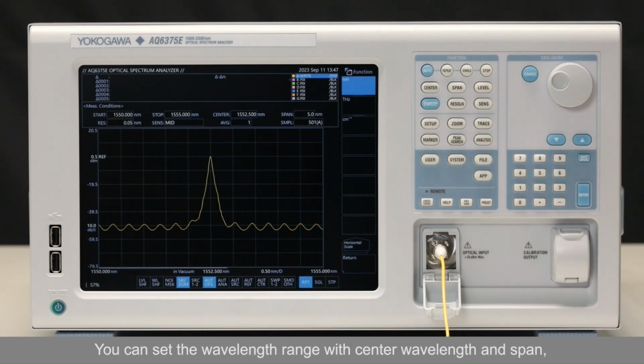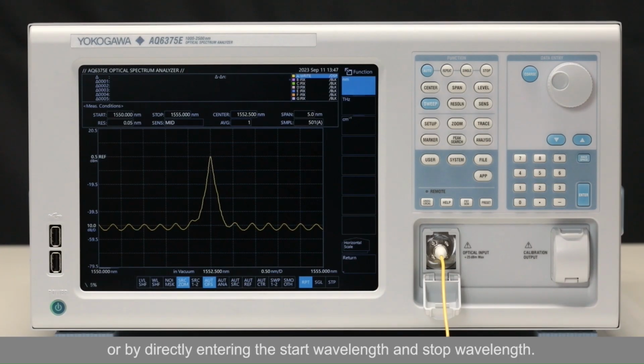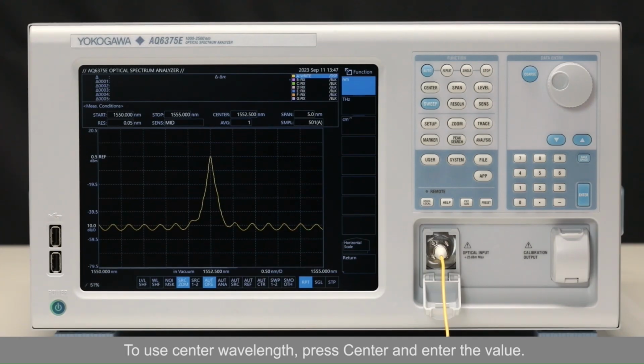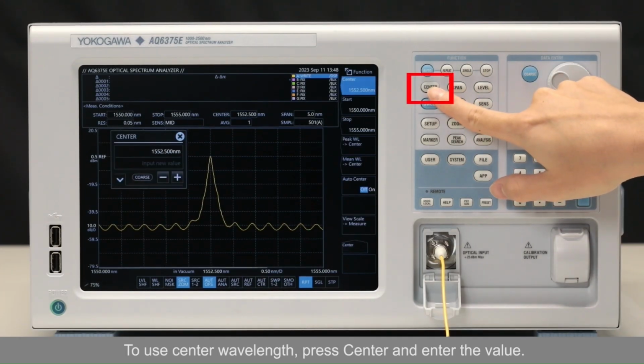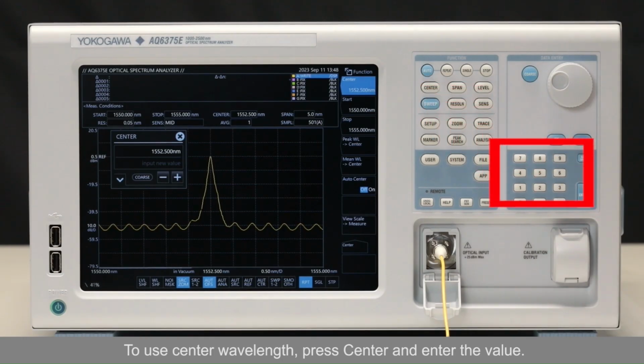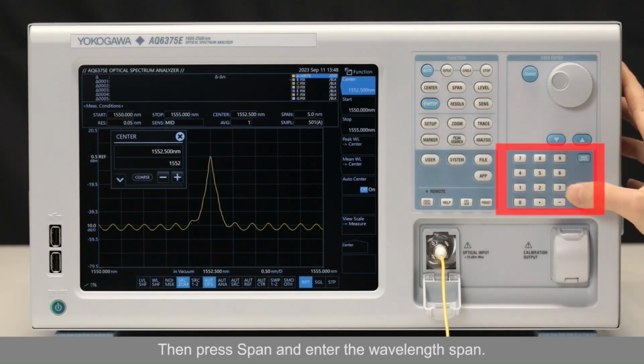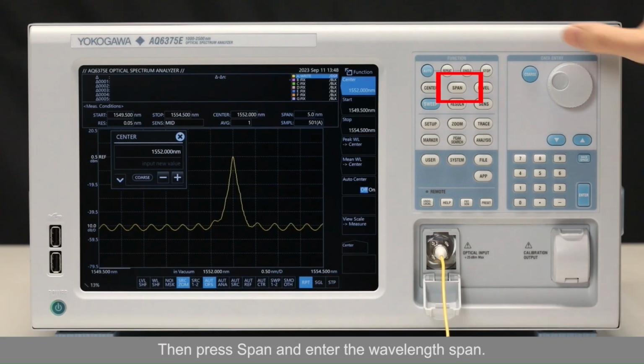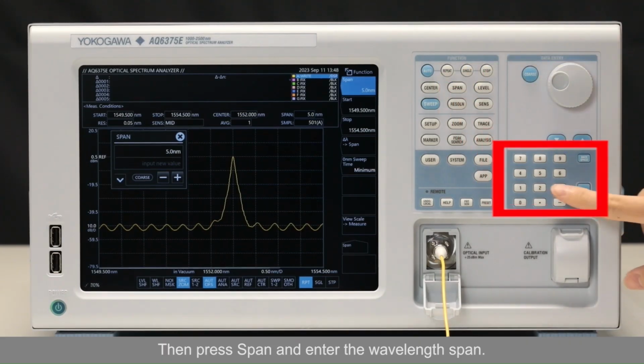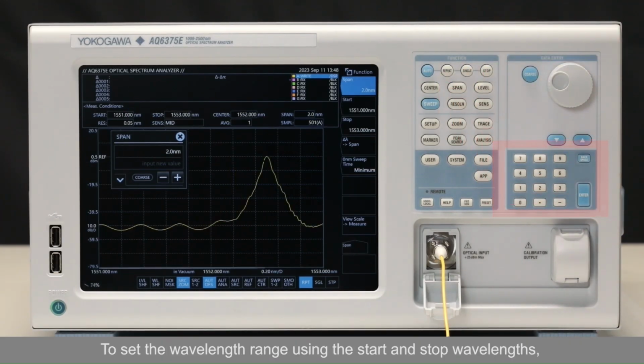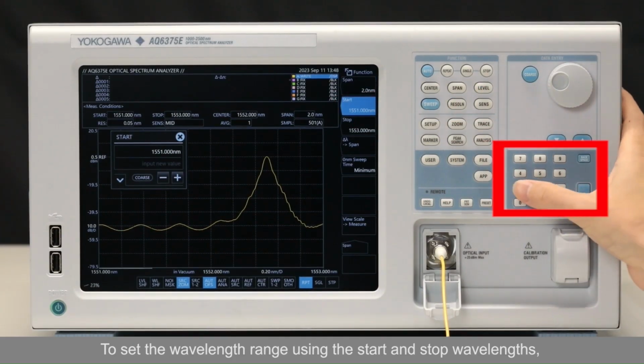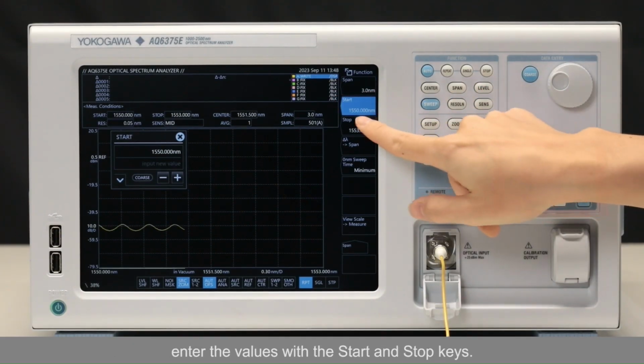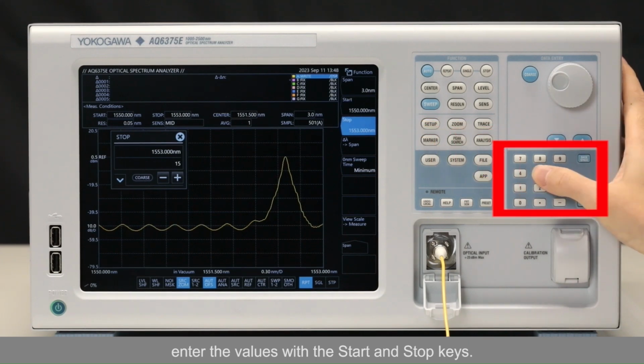You can set the wavelength range with center wavelength and span, or by directly entering the start wavelength and stop wavelength. To use center wavelength, press the center button and enter the value. Then press the span button and enter the wavelength span. To set the wavelength range using the start and stop wavelengths, enter the values with the start and stop buttons.